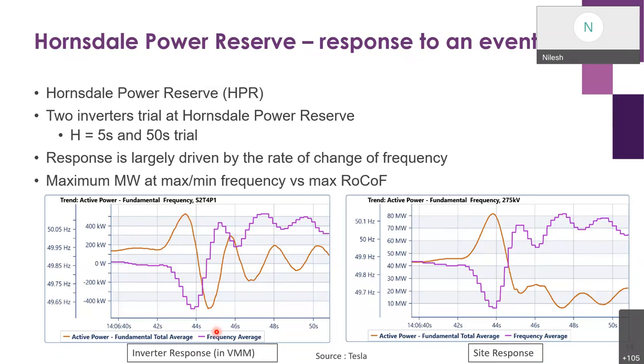When they were in a grid forming mode, the response was driven by rate of change of frequency. That is, the maximum megawatt is when the rate of change of frequency was higher, let's call it. While in a grid following mode, the maximum megawatt you get is at the frequency nadir. So it wouldn't be dependent on the rate of change of frequency.